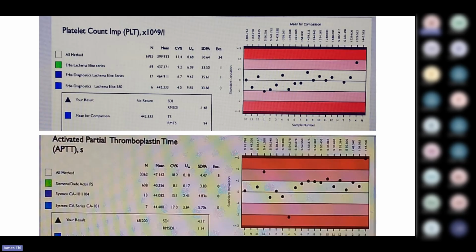My mentor once said, when she looked at my EQA some years ago, she said maintenances are not being done. That's why your graphs are scattered for magnesium and phosphate. I looked at her and I was wondering, I said, how can you? My maintenance charts are all ticked. My scientists are doing what's expected of them. It was when we got a qualified engineer that I realized that people just tick the boxes without even knowing what the maintenance procedure is or how it needs to be performed.